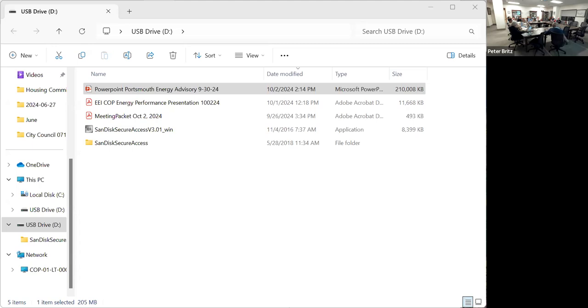So now going into some of the examples of what are the best long-term options for City Hall, there's four off the bat that we would want to evaluate financially and efficiency-wise. Variable refrigerant flow throughout with energy recovery—that's fully electric heat, but it gives you that local thermostat control for every single space. In layman's terms, it's like a heat pump system on steroids, you're getting a lot more use out of it and a lot more flexibility with the system itself. And that also has an energy recovery component to it.